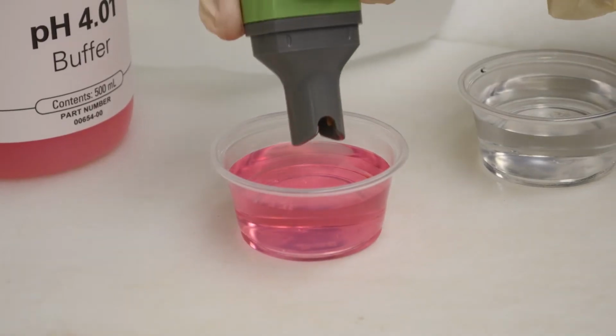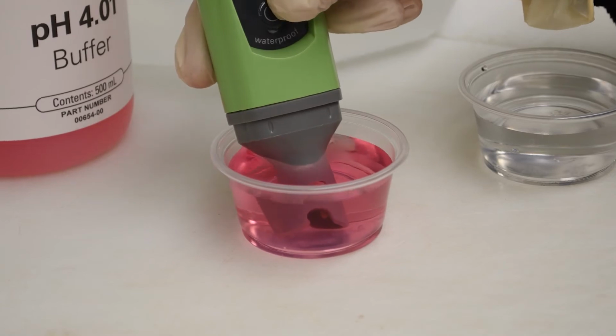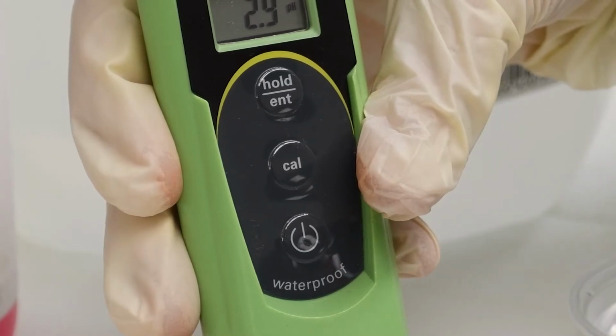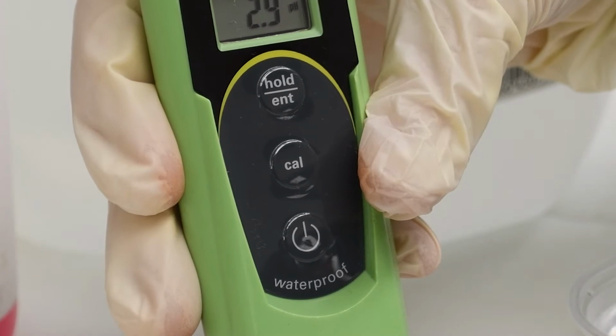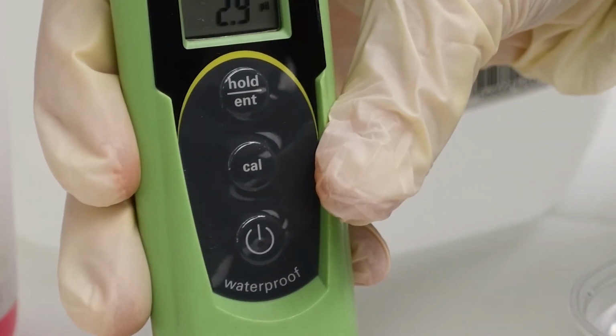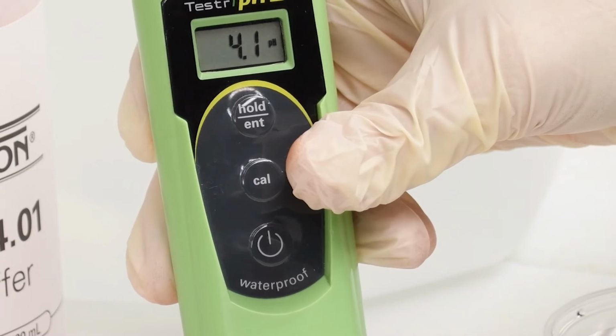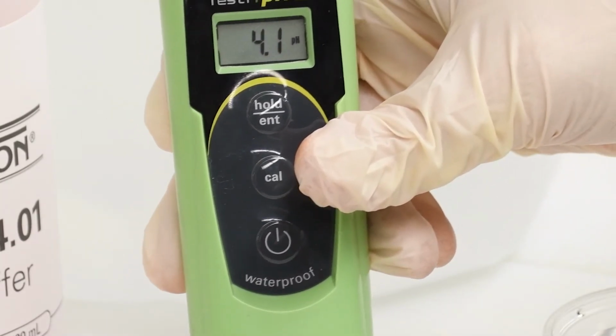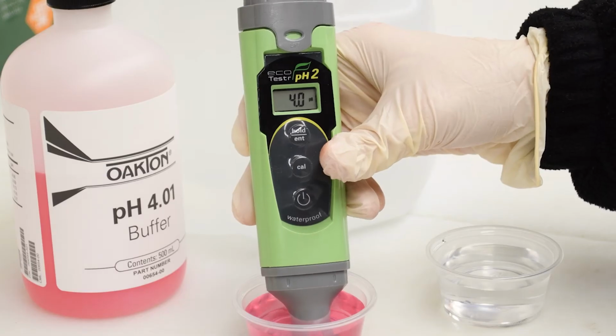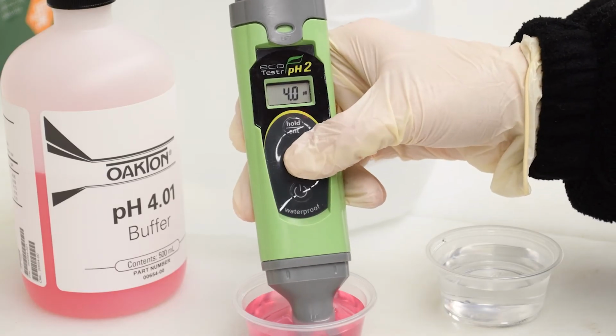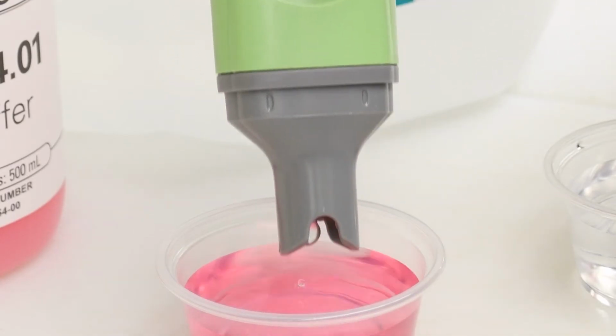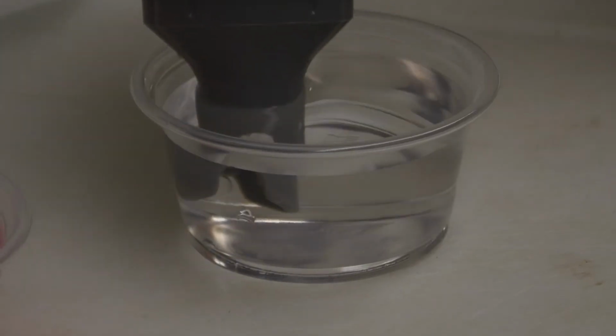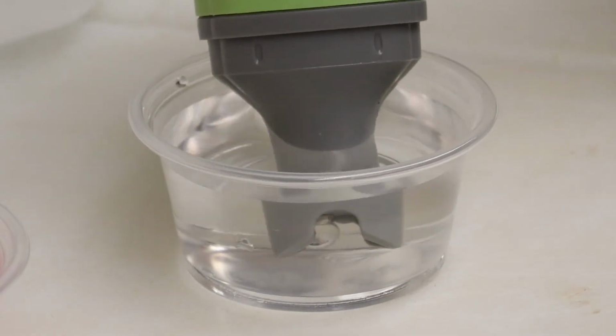Place the meter into the buffer solution, making sure the bulb sensor is completely immersed. While holding the meter, stir gently in one circular motion inside the small cup with the sensor bulb immersed enough to cover the electrodes. Now, hold the meter still and wait for the reading to stabilize. This may take up to 15 seconds. Once the reading is stabilized, press the CAL button again while the bulb is immersed in the solution to lock in the value. Remove the meter from the buffer solution and rinse the bulb off with the distilled water in the small portion cup.